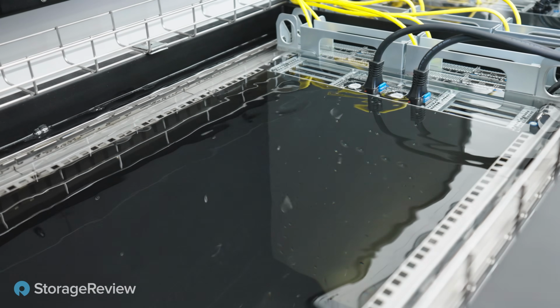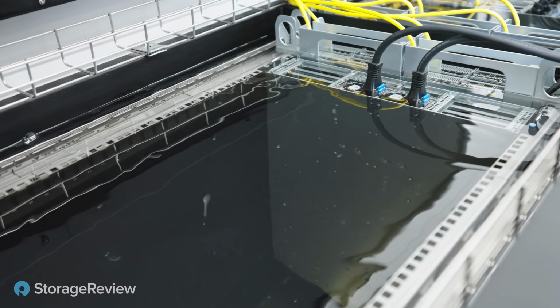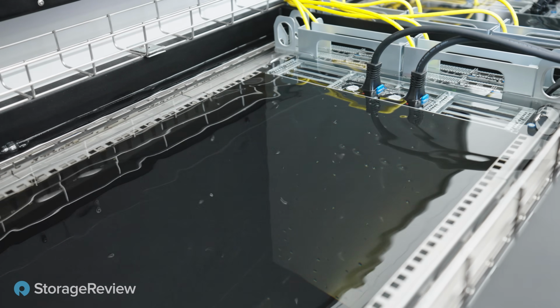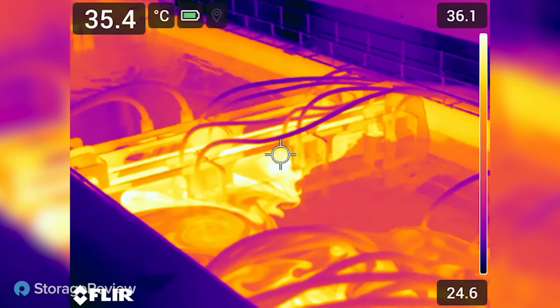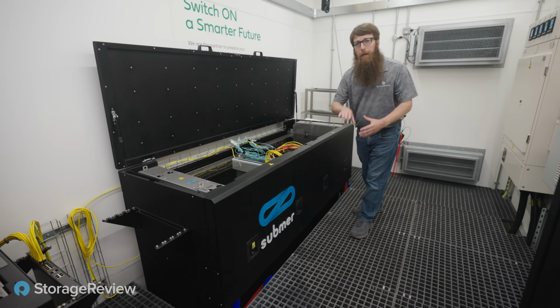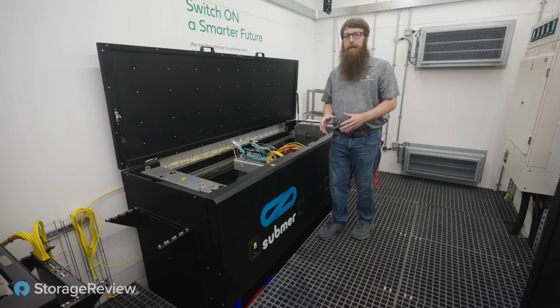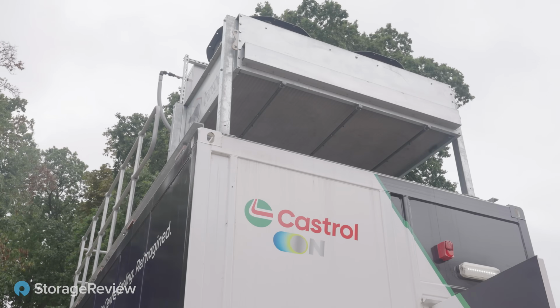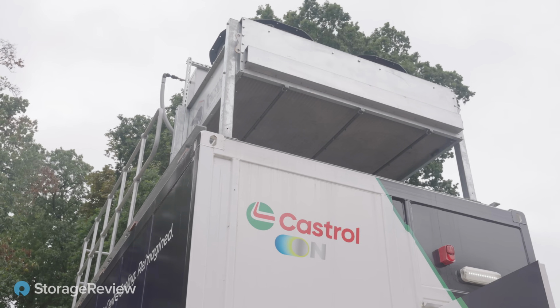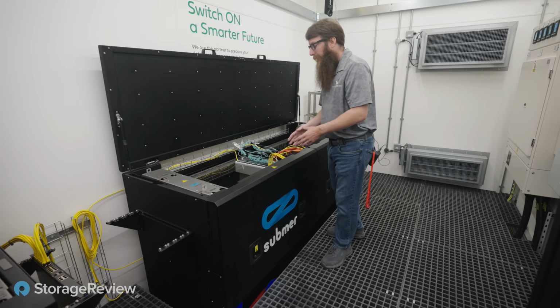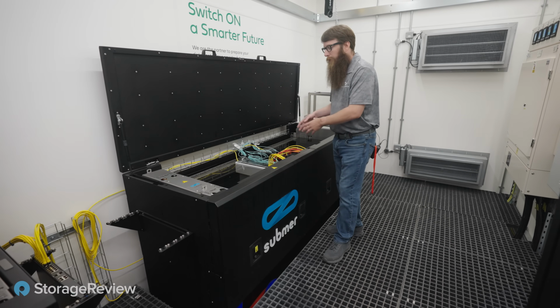Essentially how this works is this is a 42U rack with a CDU on either end. The fluid is circulated around on the inside, and there's a heat exchanger in both of those that plumb out to the facility water—whether it's a megapod like this, where everything is self-contained with a cooler on the roof, or a larger facility. These SmartPod XLs are able to plug in and keep the systems cool and operating.